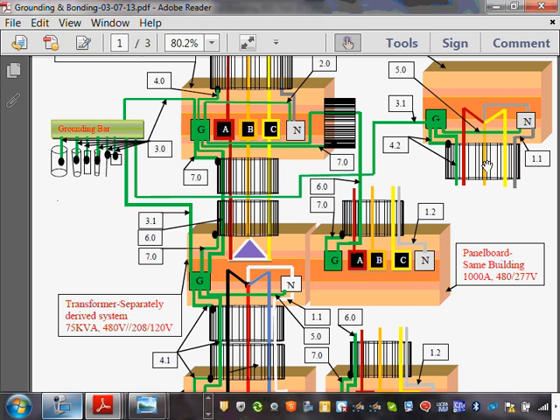But before I put that one, I want to warn you, if your generator, like the one that you did, Jeff, has the circuit breaker sitting right here, like a lot of them do, circuit breaker sitting right here at the generator, then this wire becomes an equipment grounding conductor. Depending on where your circuit breaker is sitting, this is a number 7, basically an equipment grounding conductor, sized based on the size of the circuit breaker.